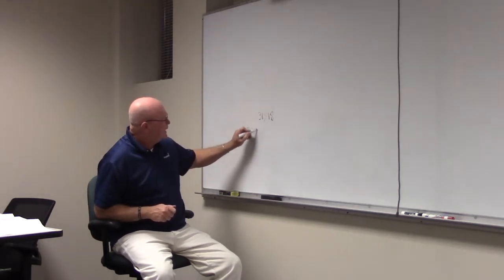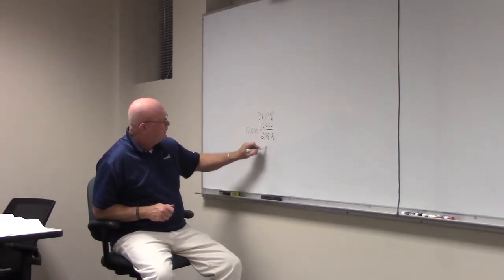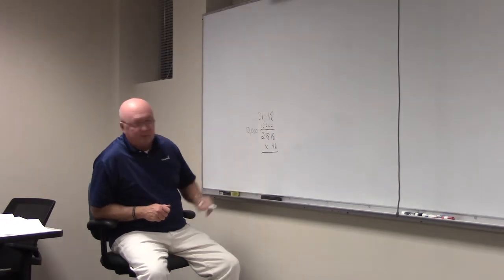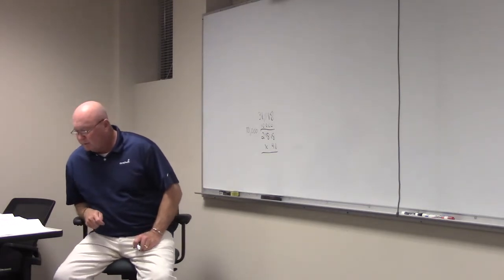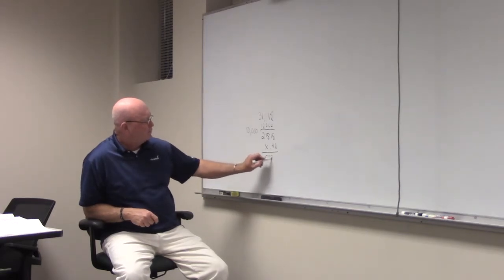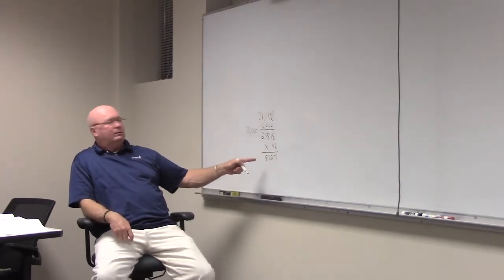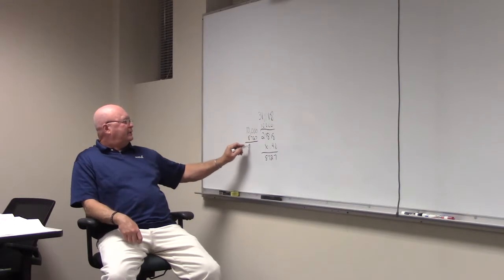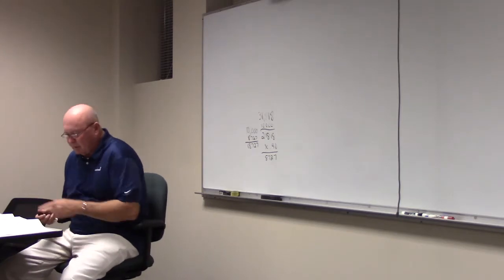And so we're going to take 10,000 out of this 31,818, right? Put it off to the side. And so then the rest of our load becomes how much? 21,818 times what? What did we say? 40%? Is that how much it was? Yeah, 40%. And what are we going to get? 8,727. What do we add that to, James? To the 10,000? Yeah. And that's 18,727. Okay, 18,727, which is what we got in our book.